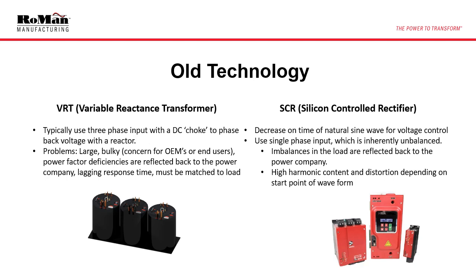In order to understand the benefits of MFDC technology, we must first understand the limitations of VRT and SCR technology. VRT stands for Variable Reactance Transformer. A variable reactance transformer typically uses three-phase input with a DC choke and a reactor to control voltage output. The typical problems with the VRTs is that they are large and bulky, have major power factor deficiencies, a lagging response time, and often must be matched to the load.